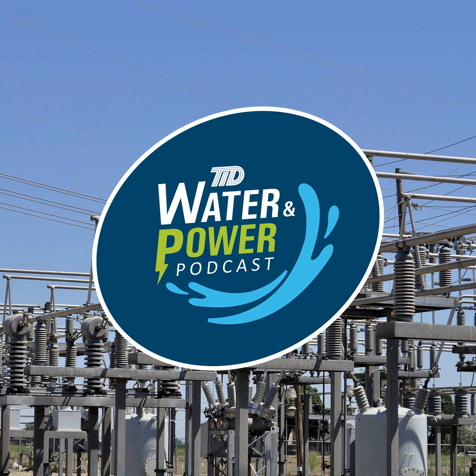Within the station, you're going to see, as I mentioned, structure. You're going to see bus, and bus is the way the current travels, the power travels through the system, either on wires or on what looks like a pipe bus. Okay. And those are supported by insulators. So you'll see either porcelain or polymer insulators. You generally see those standing on the structure, and they hold up the bus, and that's so that you have that gap to make sure that you're not going to see that fault go to ground. They also support the bus so that it is able to survive faults and anything that the system might see.